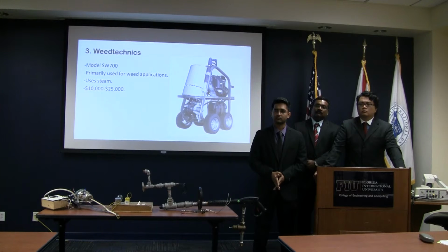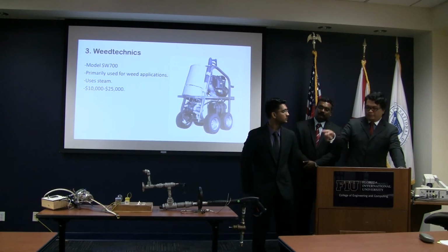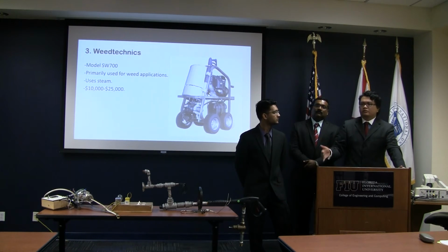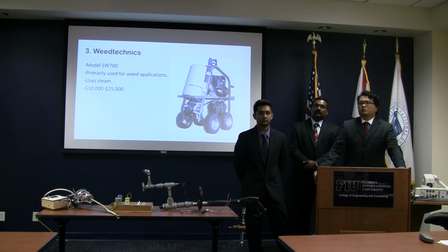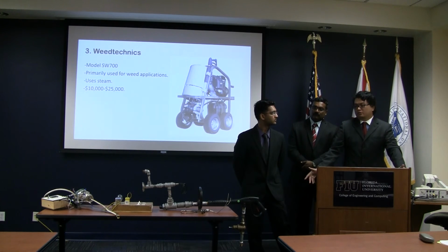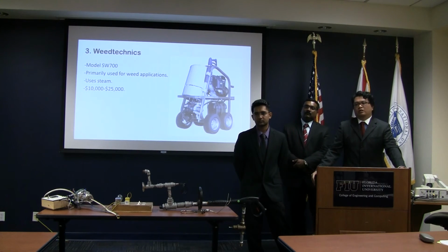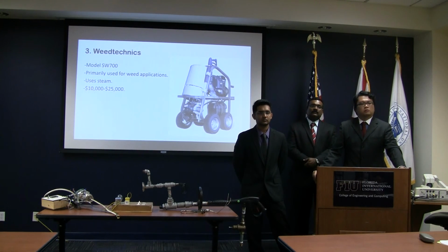Now, how was it that you started out? Did you start out with a 2000 watt heater because that's what's commonly available? Yeah. And then you work backwards and say, I want 95 degrees, what kind of flow rate and mass flow rate do I need? Is that what you guys initially did? We tested with the 1500, which is shown here. And then they only have approximately 1500, 2000, 2500. So we went with the 2000 one. And then since we already had the 2000, we just purchased another 500 to add. Yeah, it is what it is.